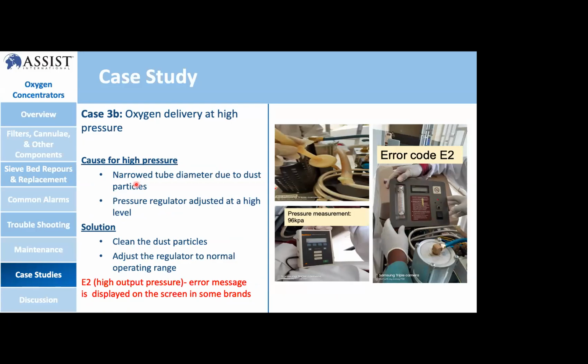Next slide. Okay, case 3B, that means in case 3, another case, now we have oxygen delivery at high pressure to the patient, or at output. So this is also another problem. The cause for this problem is narrow tubing diameter due to dust particles filling the pneumatic pathways, and the other one is a pressure regulator set at a high level.